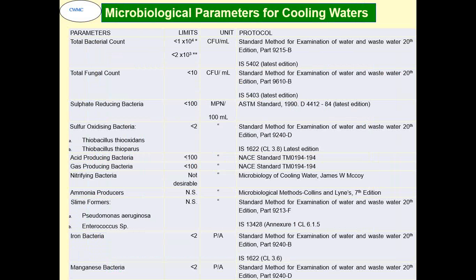These are typical microbiological limits. TBC, or the total bacterial count, should be less than 10⁴ CFU per ml, preferably less than 2 into 10³. TFC less than 10 CFU per ml, SRB less than 100 per 100 ml, sulfur oxidizing less than 2, acid producing less than 100 per 100 ml, that means less than 1 per ml, gas producing bacteria less than 1 per ml. Nitrifying bacteria not desirable, ammonia producer not specified but not desirable, slime formers again not specified but not desirable, iron bacteria less than 2, manganese bacteria less than 2. I have given the protocol also by which they are tested.